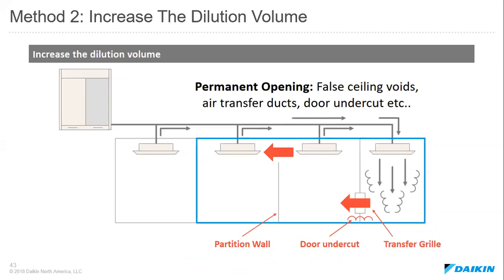Then finally, another way to increase the dilution volume would be to have a permanent opening between the rooms. This could be a false void ceiling, or it could be done through air transfer ducts, transfer grills, which is done quite a bit, or through door undercuts or a partition wall. That also will allow us to, once again, increase our dilution volume by counting all the rooms as one singular space.